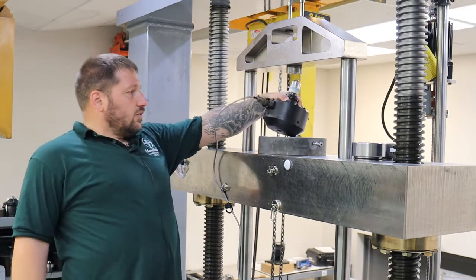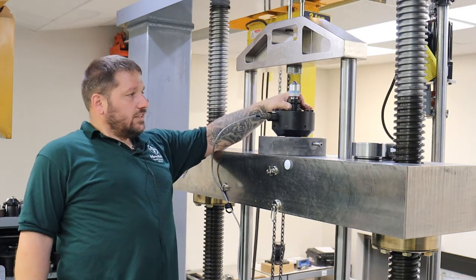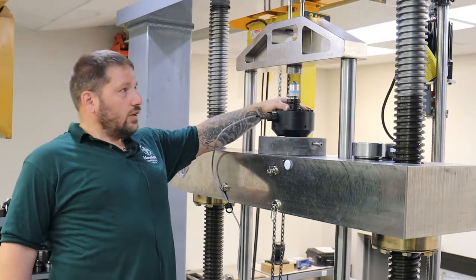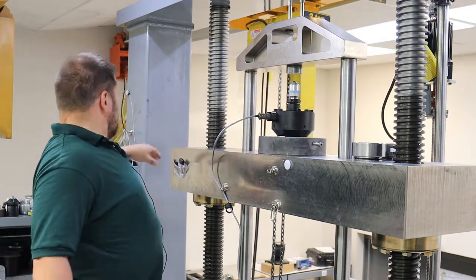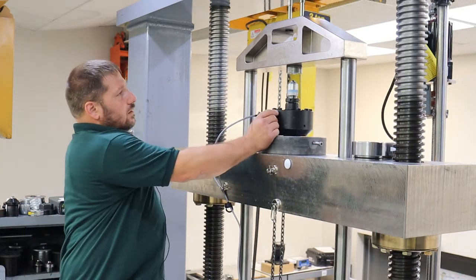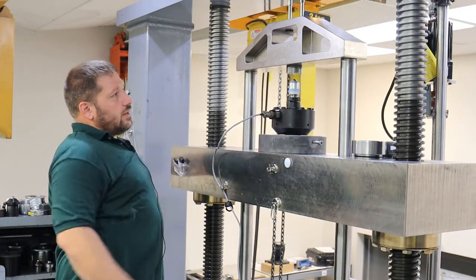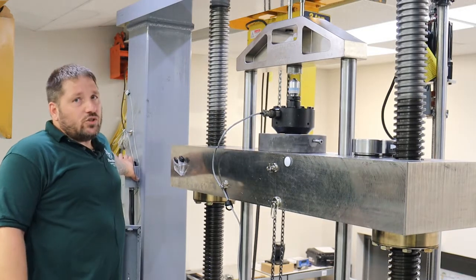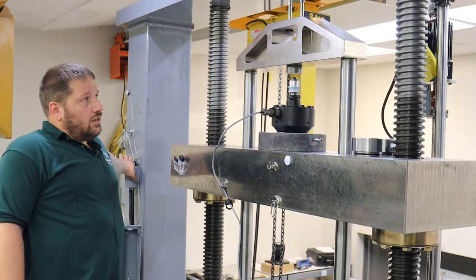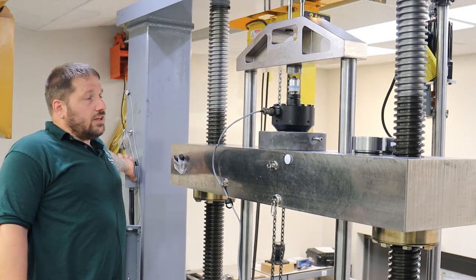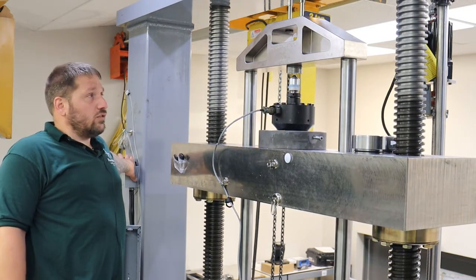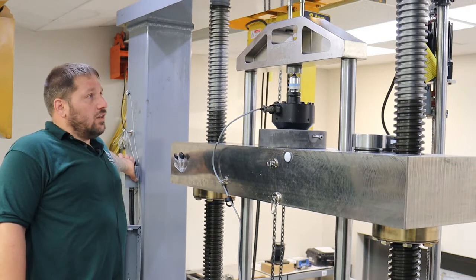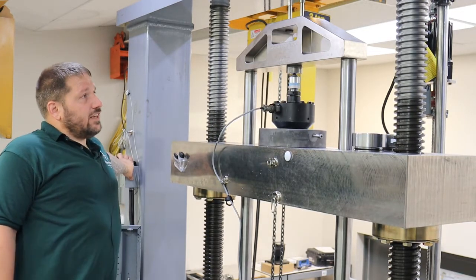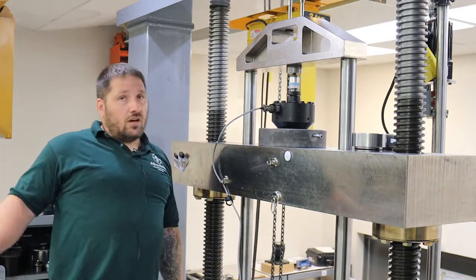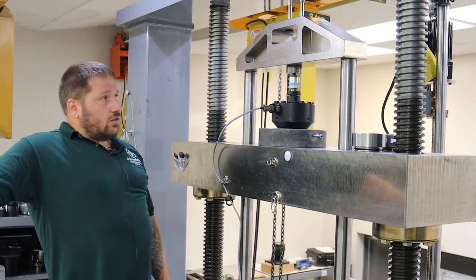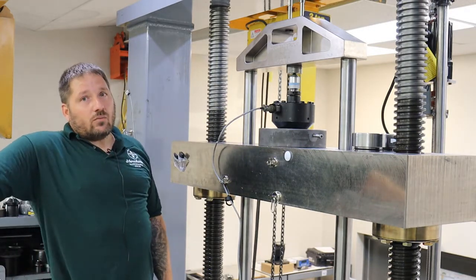So I set the load cell here. This is how we do it at Morehouse. We load against the base. An important thing to know is anytime you send your stuff in for calibration, it's a good thing to tell the calibration company how you load your load cells in-house, because you could see a significant difference in the readings depending on how you load it. So it is really important to let your calibration company know that.